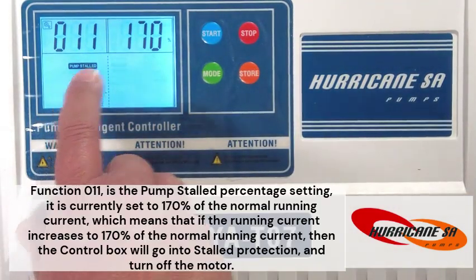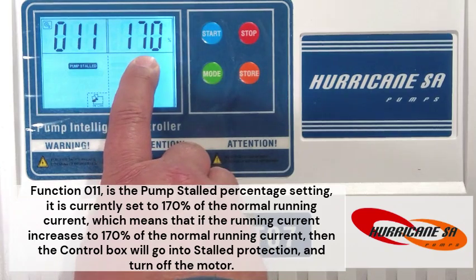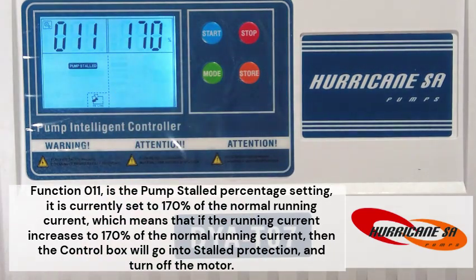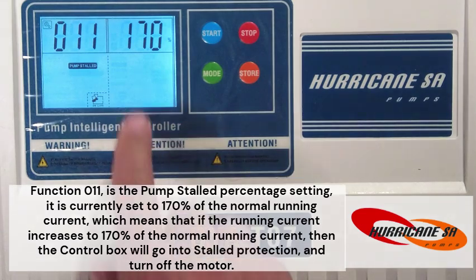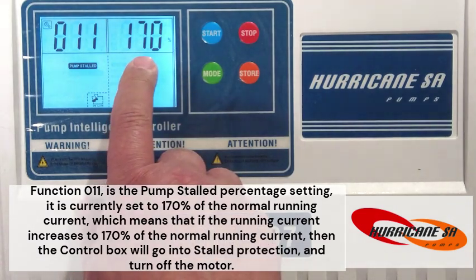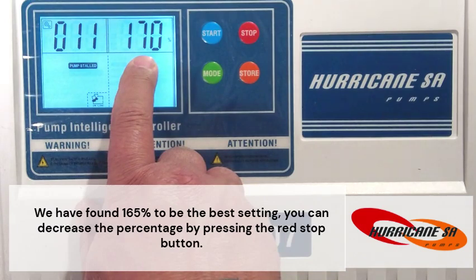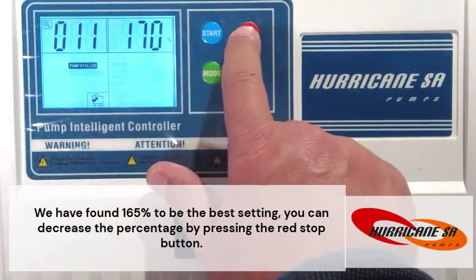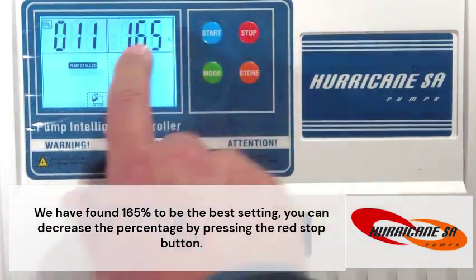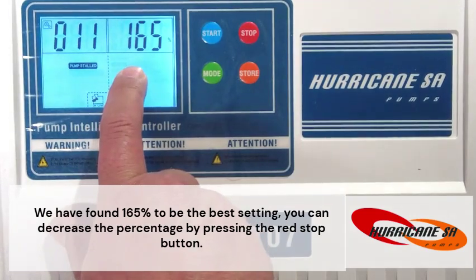To enter function 011, we'll push the orange store button once. Function 011 is the pump stall percentage setting. It is currently set to 170% of the normal running current, which means that if the running current increases to 170% of the normal running current, then the control box will go into stall protection and turn off the motor. We have found 165% to be the best setting. You can decrease the percentage by pressing the red stop button.